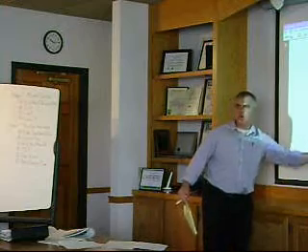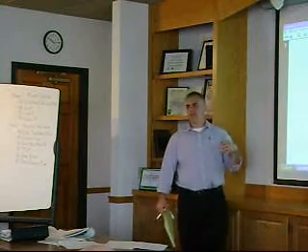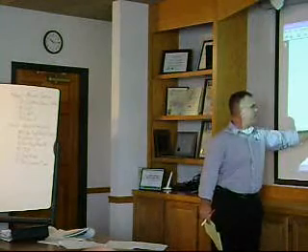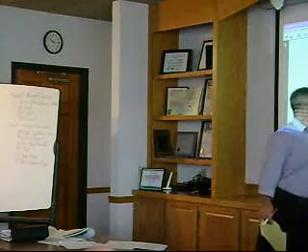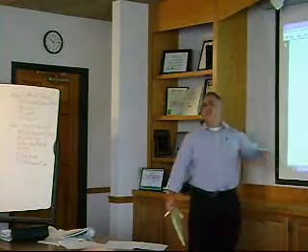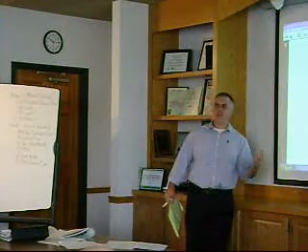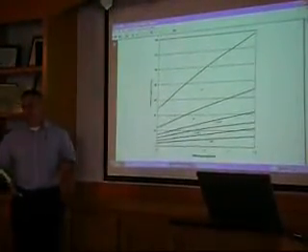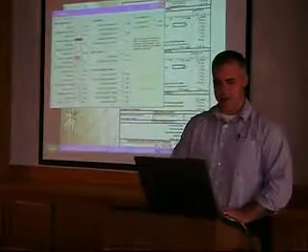Once you hit that number, you've exceeded the 10% variation difference. With 2-inch pipe and 2-foot hole spacing, you go to 60 feet. So you've got to choose the pipe diameter that fits your job based on hole spacing and length of the lateral.